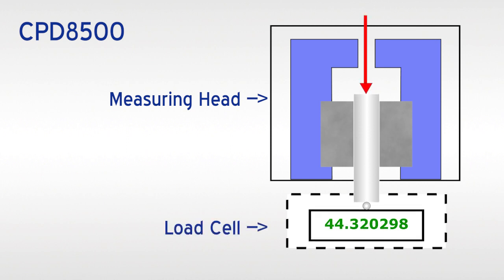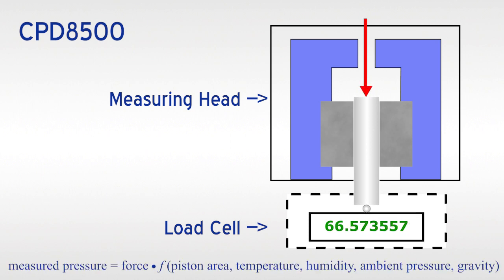The unique operating principle follows the fundamental concept of a piston gauge. The pressure is applied on the measuring head to the effective area of the piston and is converted into an equivalent force. The force is transferred to the measuring load cell housed within the base. The load cell continuously measures and calculates the pressure generated force. The base converts the measured force to the equivalent pressure and corrects for environmental influences.